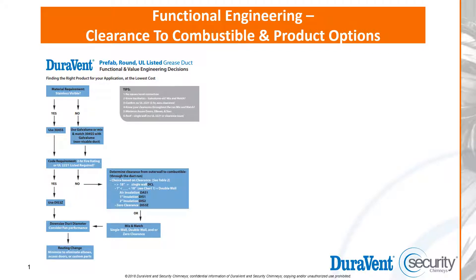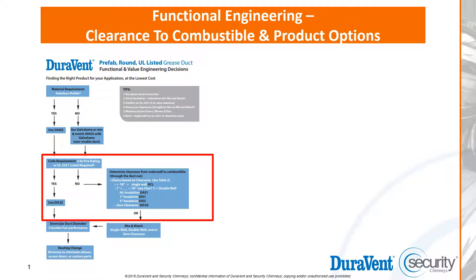Good day, we're going to talk about clearance to combustibles and product options. This is Joe, and we're talking about this section of the design process. The reason we're doing that is grease duct does not equal zero clearance — we see a lot of over-designs out there, and we're really just adding cost to the project unnecessarily.